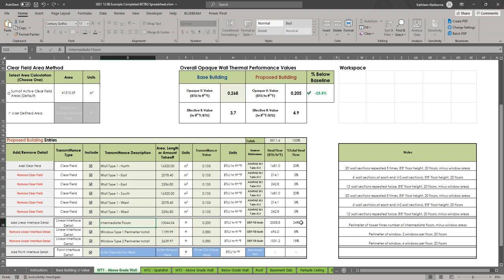The other thing is that as you do more, as Andrea mentioned, you do more of this type of analysis and calculation, then you'll start to recognize the things that impact thermal bridges. When you have concrete touching concrete and there's your whole wall thickness of it, that's a big thermal bridge. If you have two different wall assemblies, say this one has 3 inches of insulation and this one has 6, that's technically still a thermal bridge, but it's going to be a lot less because you're still insulating continuously. So, to reiterate, the thermal bridges are actually where your heat loss changes. Even on something that is completely insulated, you'd still have a thermal bridge, technically. And that would certainly not be good.